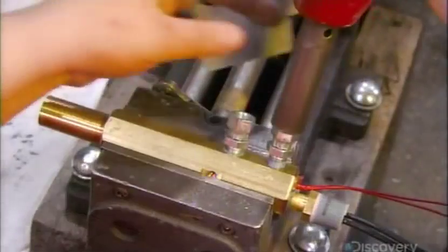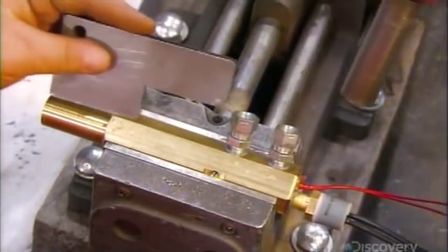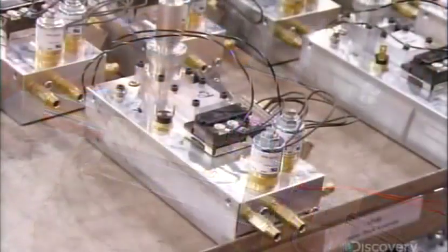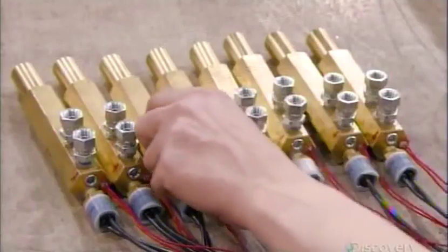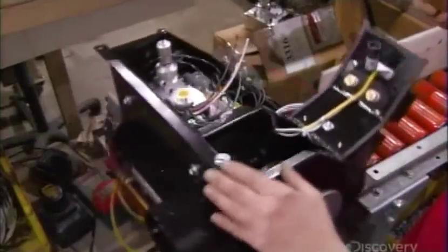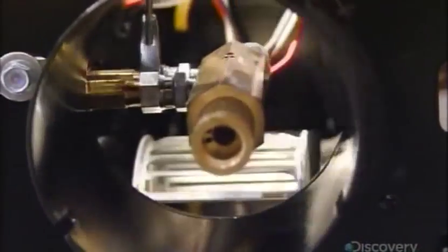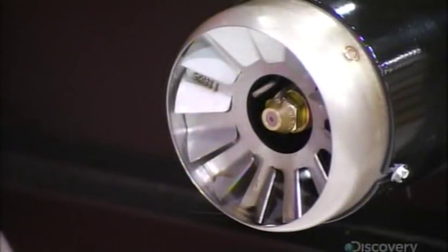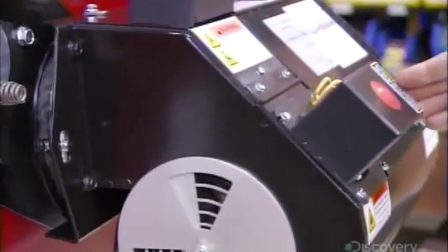She checks these fittings with a leveling tool to ensure the adapter will go on straight inside the housing. She also installs an assembly that controls oil flow, temperature, and air pressure. Then she mounts the nozzle adapter and covers it with a retention head that shapes the flame for optimal heat, completing the burner assembly.